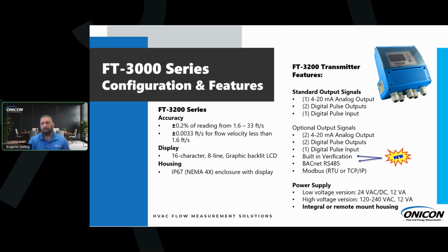Another thing I want to mention about the remote mount cable is a lot of the times we'll have a customer that orders it for, say, 50 feet, but they only needed 25 feet away. Instead of cutting that cable, because this is a very special cable that is very sensitive, and we're picking up these small voltages within the meter body, right? We suggest it be coiled up and put in a separate junction box. We do not recommend cutting it in any way. That will void the warranty on that cable.